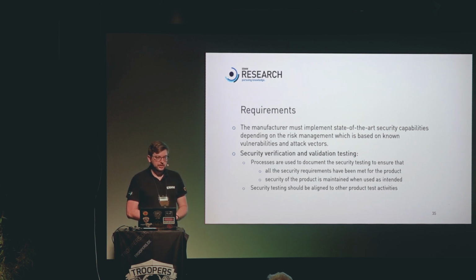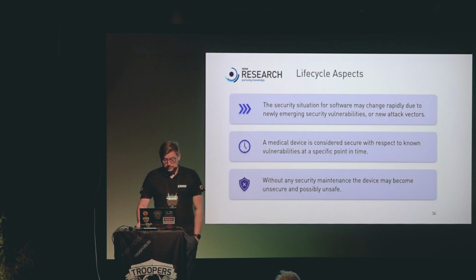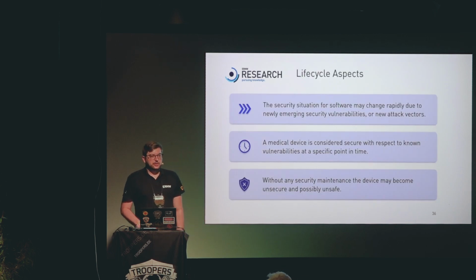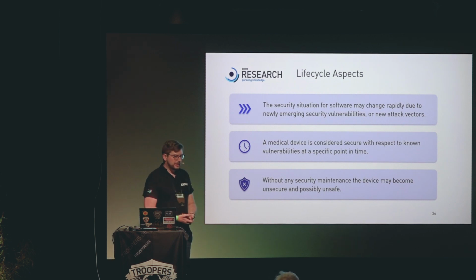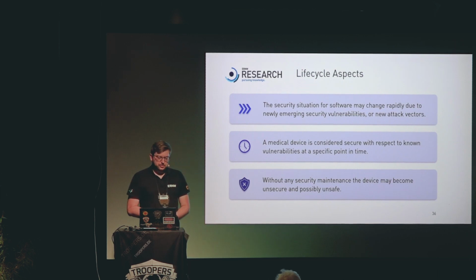So that really needs to be in the DNA of that device in the end, and in your processes, where you're doing verification testing by means of security testing. And also the MDCG is telling the manufacturers, I think, no-brainers about the life cycle aspects, because it's telling you that a device can only be considered secure at a dedicated moment in time, and if you don't do anything and don't add further security functionality, or you're patching your bugs and not assessing that, then it's just secure for that moment, and it may be vulnerable 5 minutes after that.